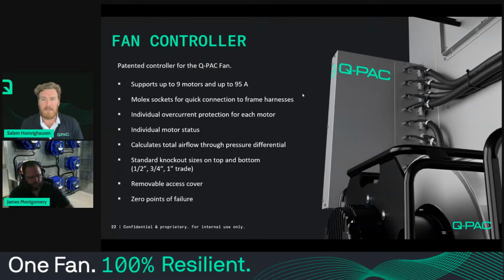The fan controller - this is really the brains of the product and what has enabled us to re-architect everything. It started out as a consolidation point for all the power controls, and it has evolved into a product that actually controls the individual motorized impellers. You get individual overcurrent protection for each phase of each of the ECMs, plus other features.